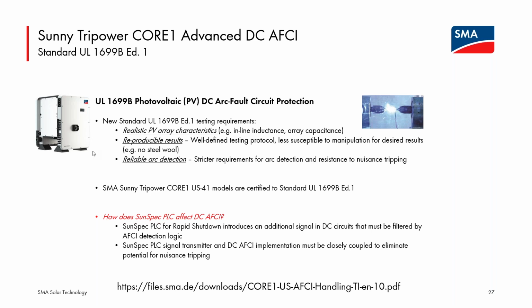And is it 1,000 volts input per MPPT or 1,000 volts total between all 6? Any input, so any string, any channel, each and every one can go up to 1,000. None can exceed 1,000. Are there string level rapid shutdown receivers that work with SMA inverters?